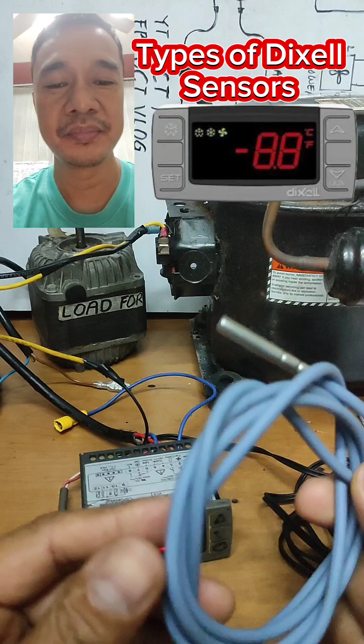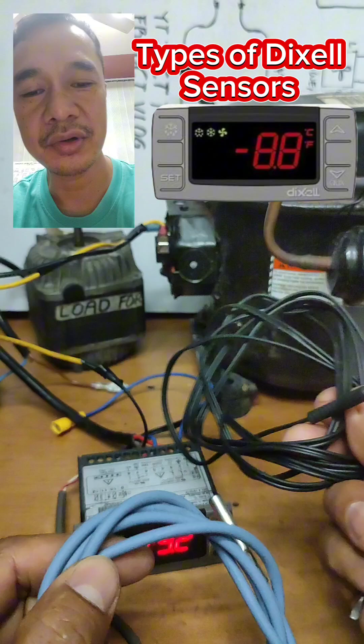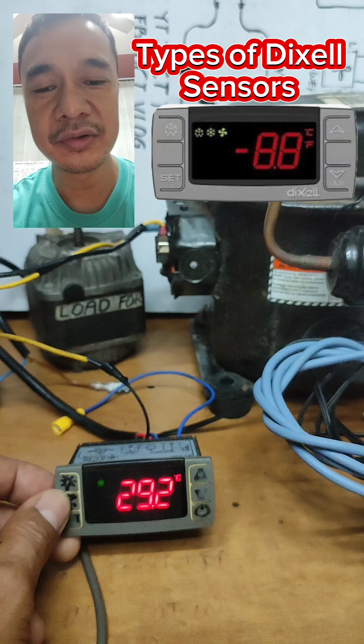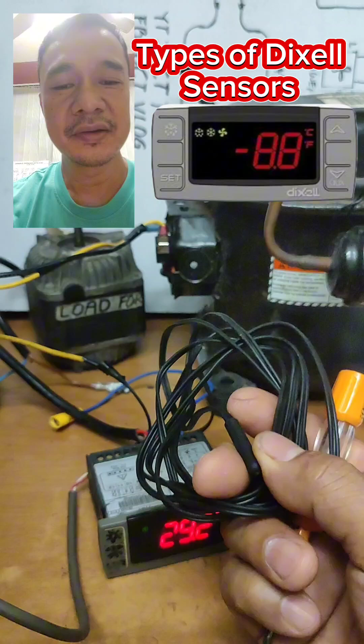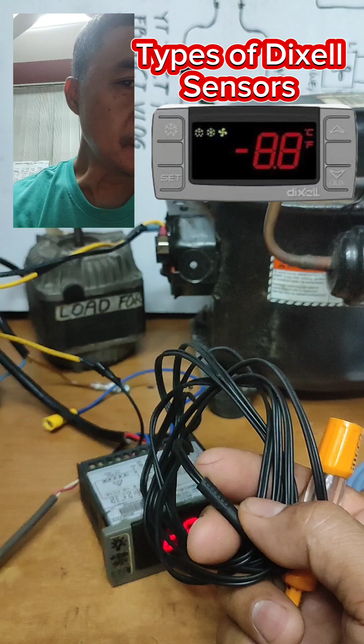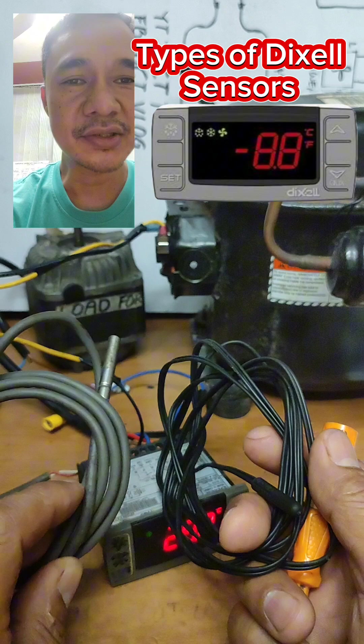A while ago, we mixed NTC with NTC for the evaporator and room sensor, but set the PBC parameter to PTC, and we got a problem. Then we set PBC to NTC but used a different type of sensor, and we still got an issue.